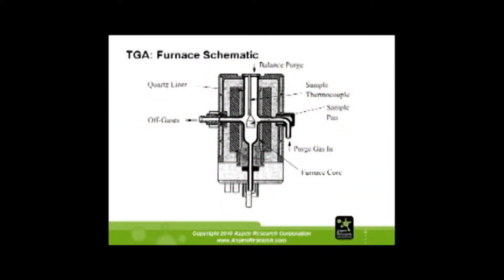Here's a close-up of the schematic. This is a quartz liner. Your purge gas comes in here and goes out this way. Your sample pan sits right here. Your thermocouple actually comes down a little further — it should come down right into here so that both the sample and the thermocouple are seeing the same temperature.